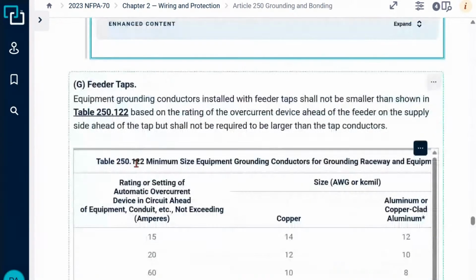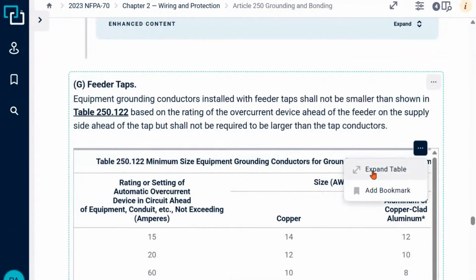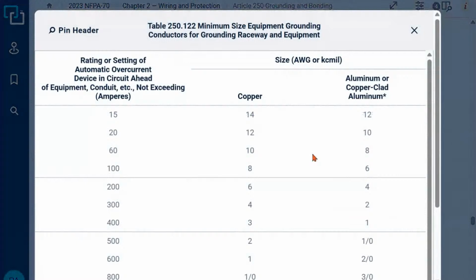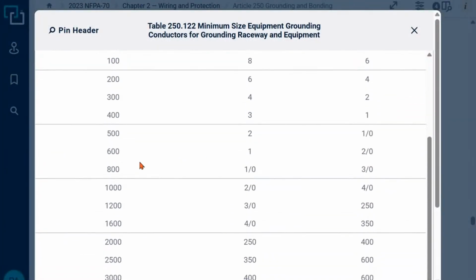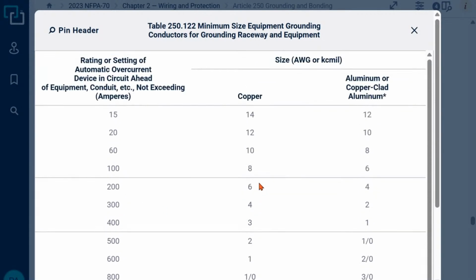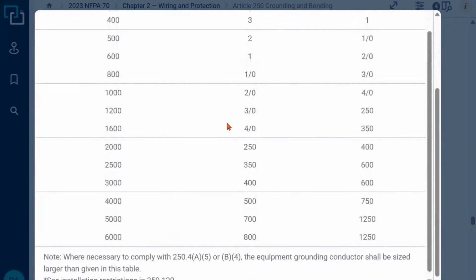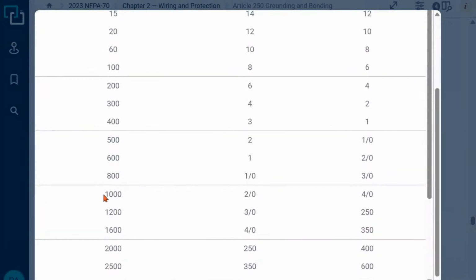Anyway, that's what we're talking about. All right, so let's go to the table. So here's the table. Let me pop this up. So this was a 1,000 amp overcurrent protected device right there. In copper, it says a 2-aught, right? Because we're doing copper. And this is the minimum size equipment ground. So we have a 1,000 amp overcurrent device, 2-aught copper. Let's go back to the lesson now.